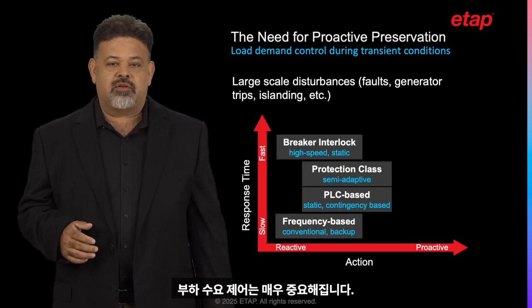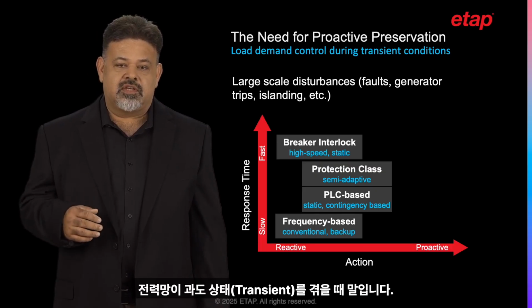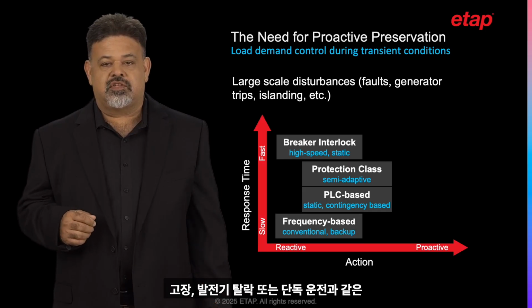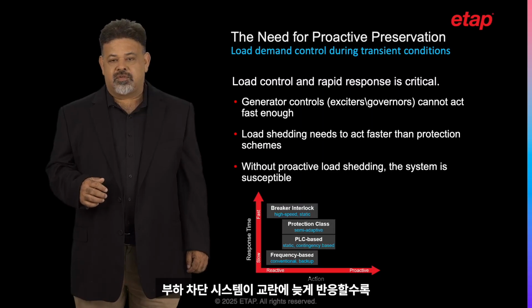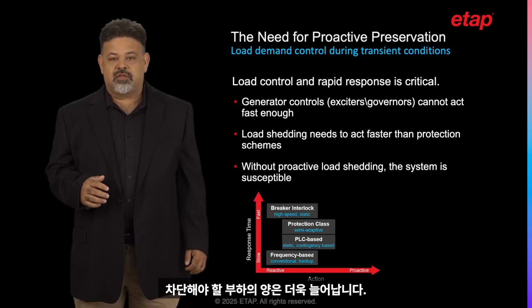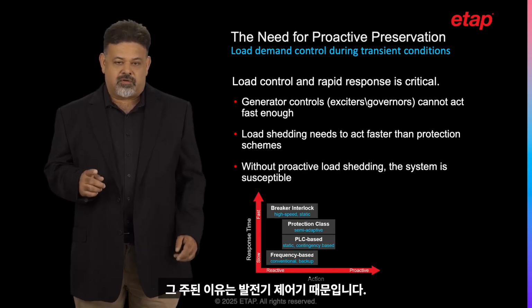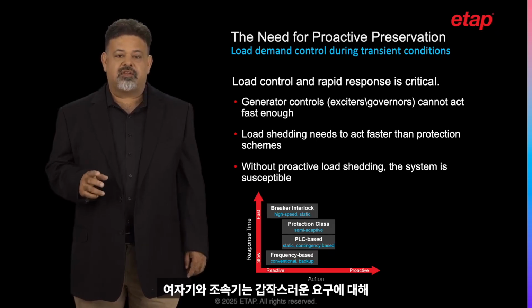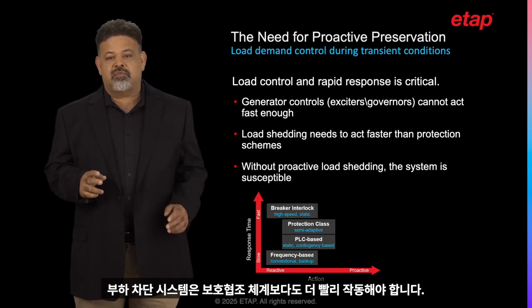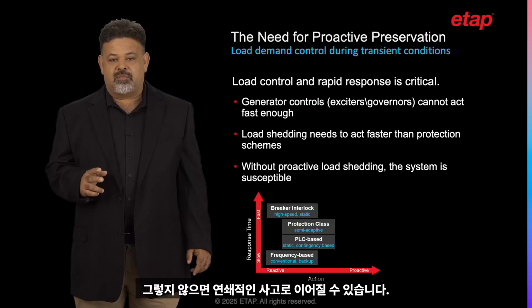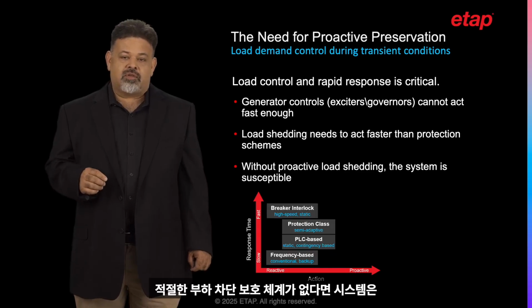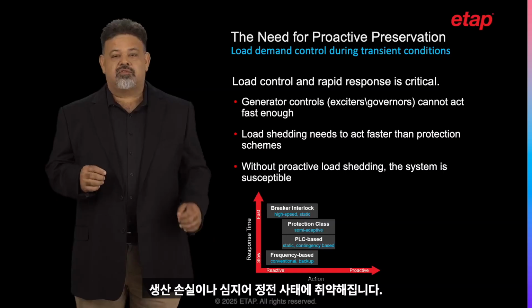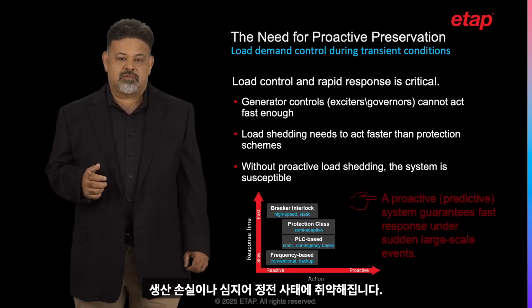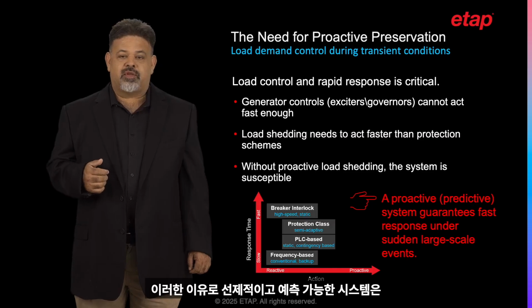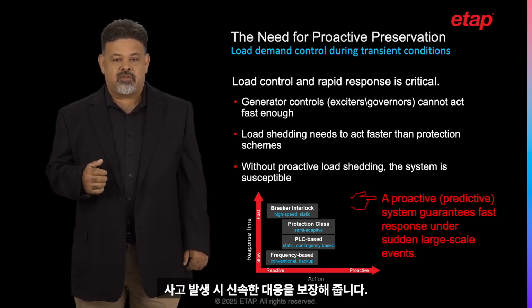Load demand control becomes critical when the electrical network goes through transient conditions. Any system is susceptible to large-scale disturbances such as faults, generator trips, and islanding. The longer the load shedding system waits to react to a disturbance, the more load is required to be shed. The reasons for this are primarily the generator controls. Exciters and governors cannot act fast enough to these sudden requirements. The load shedding system needs to act faster even than the protection schemes, as they may cascade into further events. Without a protective load shedding scheme, your system is susceptible to loss of production and even blackouts. For these reasons, having a proactive predictive system will guarantee fast response under such events.